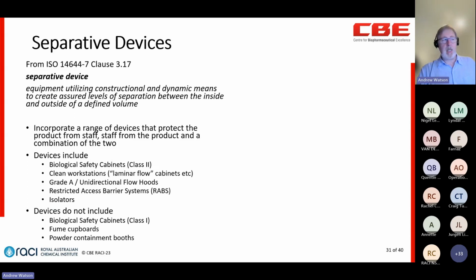This is a list of some of those things: biological safety cabinets, isolators, RABS, those sorts of things. It doesn't include class 1 biological safety cabinets, fume hoods, or powder containment booths — those are typically things where you stand in front, and they only provide operator protection. If you've got a clean product in there, as I saw the other day, all the air's passing past the personnel doing the work and contaminating your product.